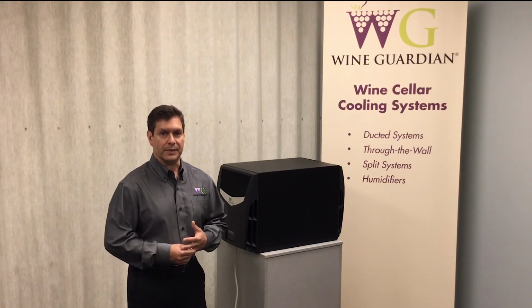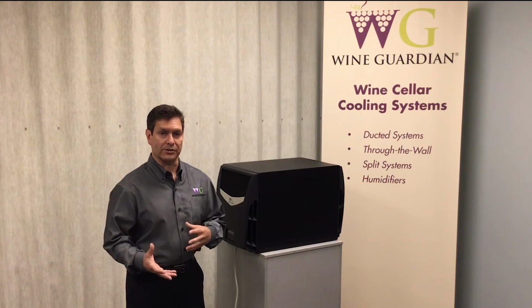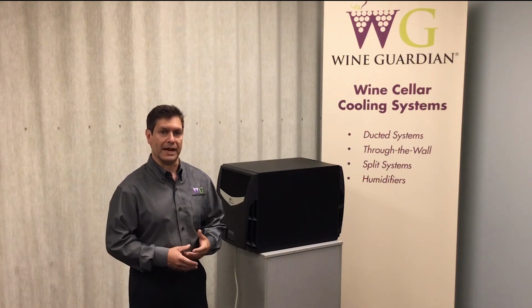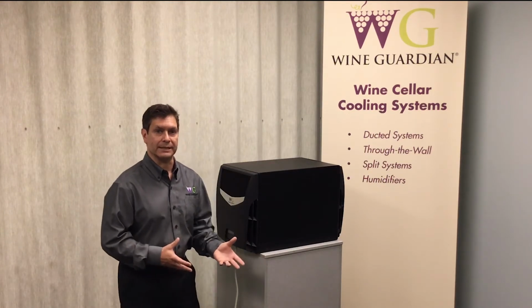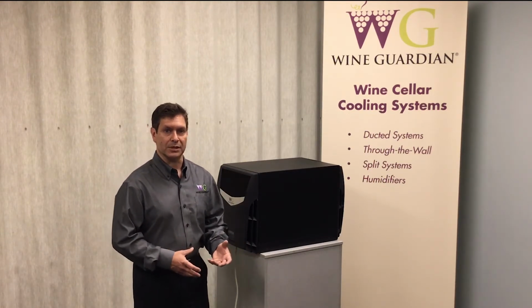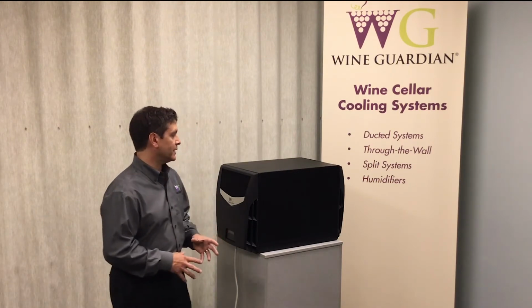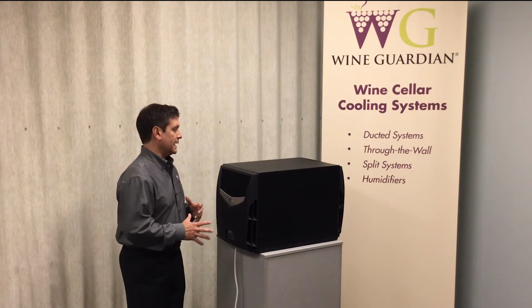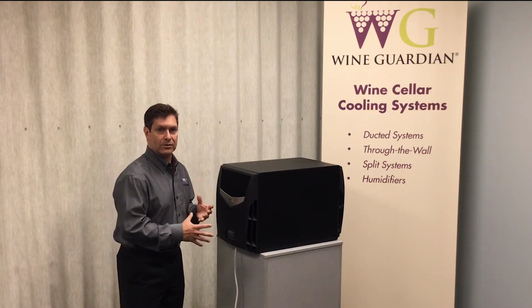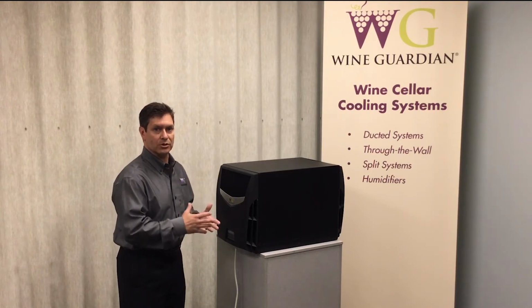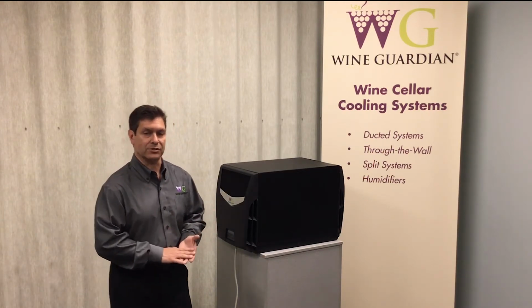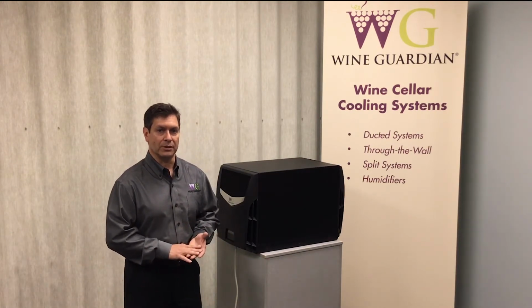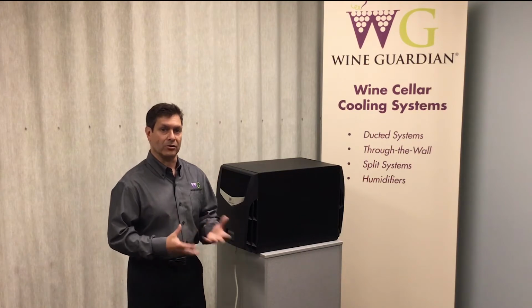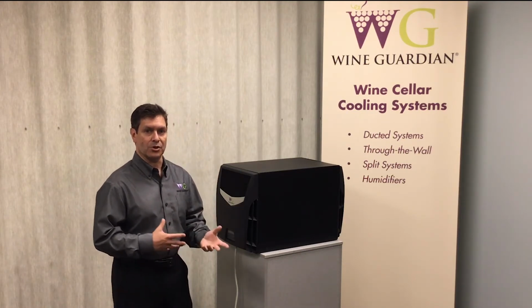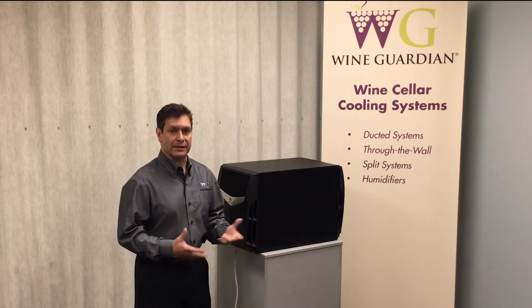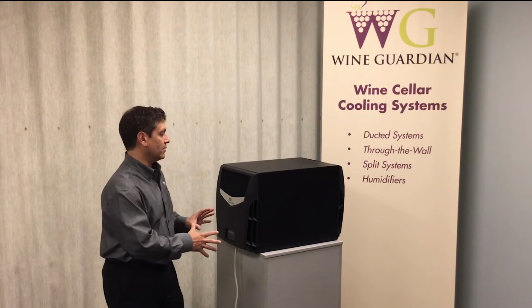Generally, there is a cold air side and a warm air side. The warm air side would typically vent to an indoor space, and that's exactly how our systems are designed. It is a self-contained unit by all means, and what that means is all of the mechanicals are in one device. So you'll have your compressor, you'll have your condenser coil, you'll have your evaporator coil, you'll have evaporator fan, condenser fan, and all of your controls in one device. So there's no auxiliary equipment outside of the building, outside of the structure that you have to tie into. It's all right here in one package.